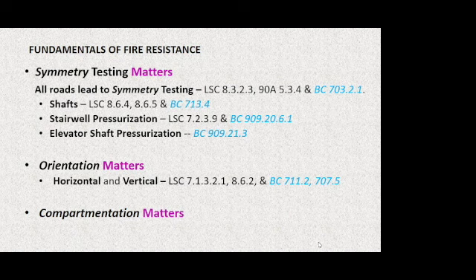So symmetry is one of those fire resistance concepts. And we find that all of the code paths that we're going to talk about related to fire rated duct systems, other than grease duct, it might be 1 step, it might be 2 steps, it might be 5 steps to go from one code reference to the next. But you're going to find that they all land at 703.2.1, which is a pivotal paragraph, because this is the paragraph that says you must test the assembly to the fire resistance test standard. And we're going to make that citation at the appropriate juncture.